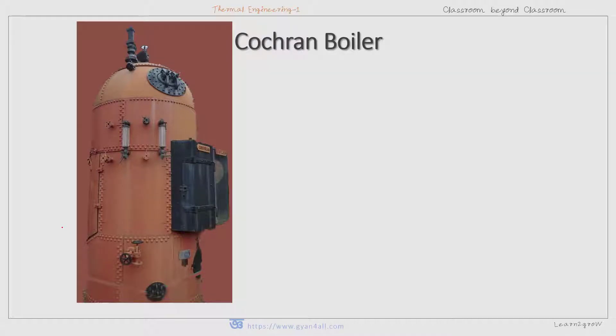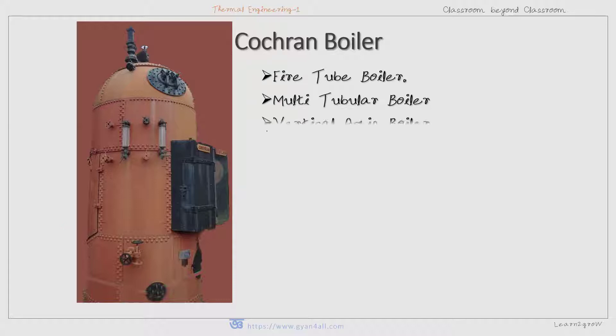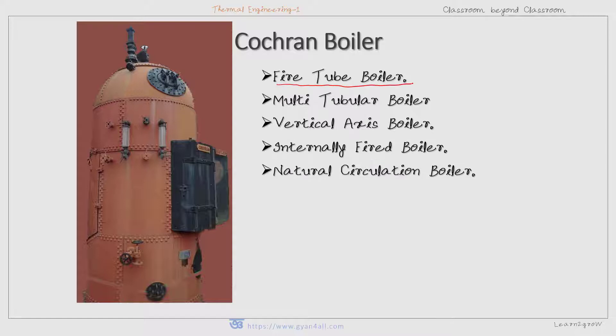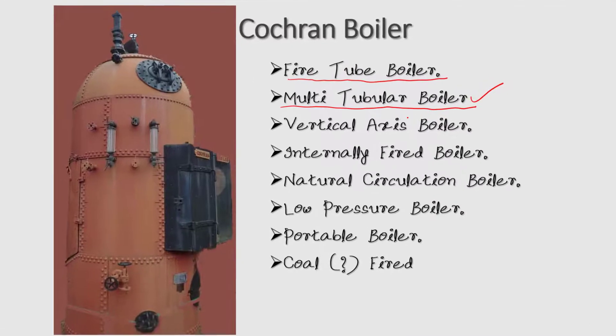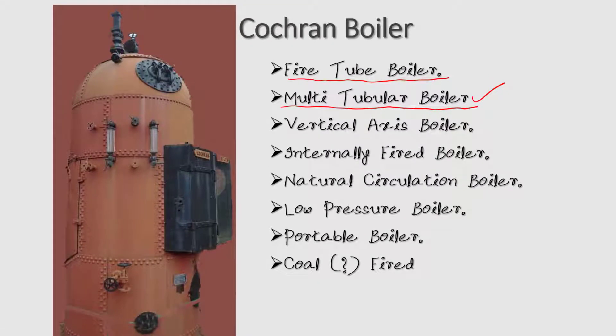Let us understand the Cochran boiler from the point of view of classification. The Cochran boiler is a fire tube boiler. It is a multi-tubular boiler — the simple vertical boiler is a single tube boiler, but the Cochran is its modification, so it is multi-tubular. The axis is vertical, so this is a vertical axis boiler, and it is an internally fired boiler.